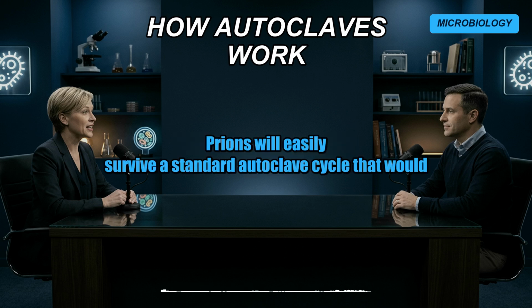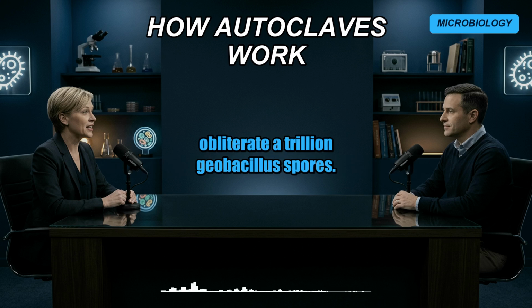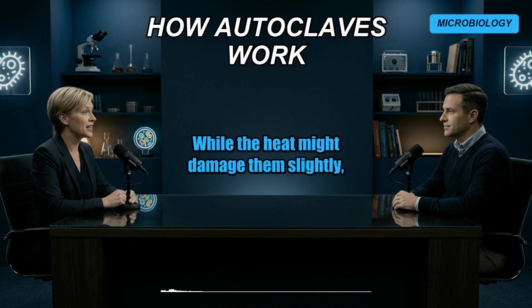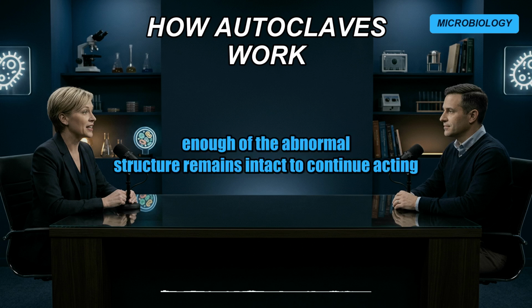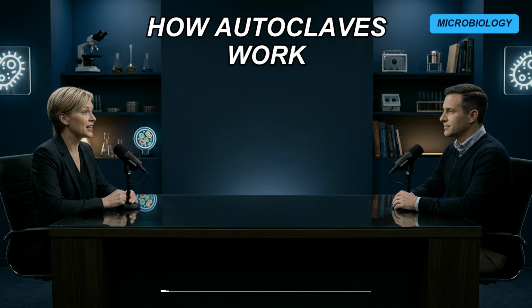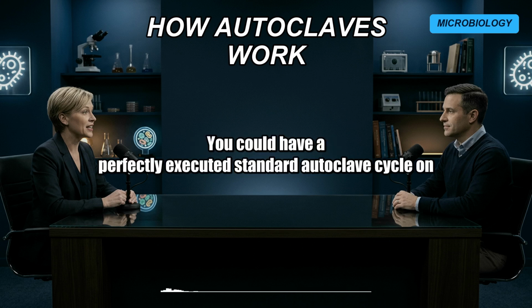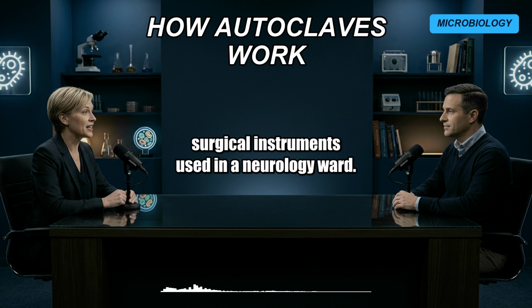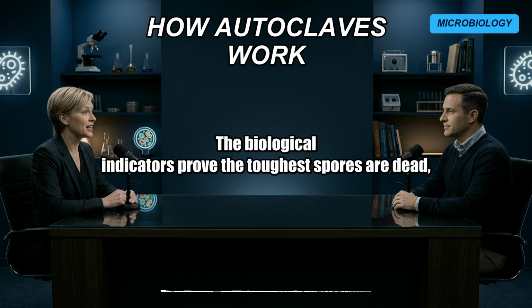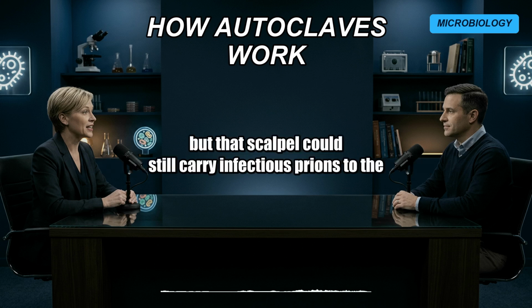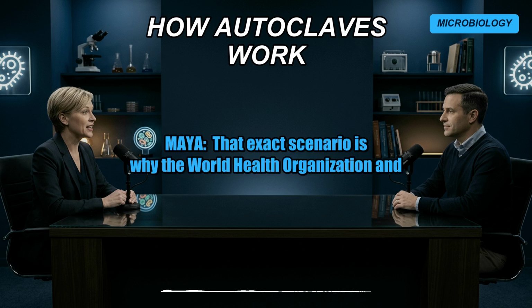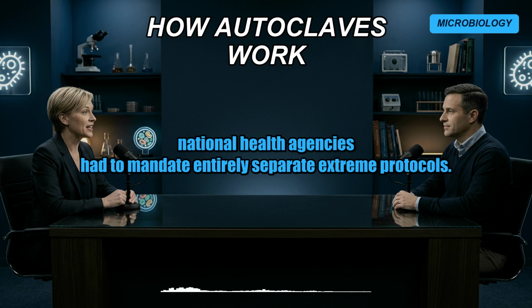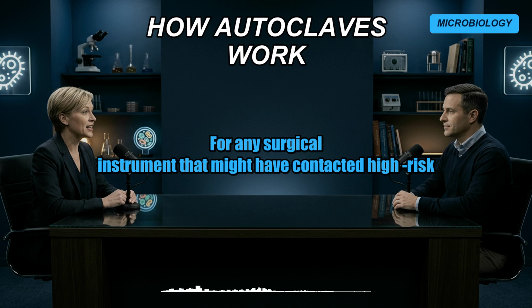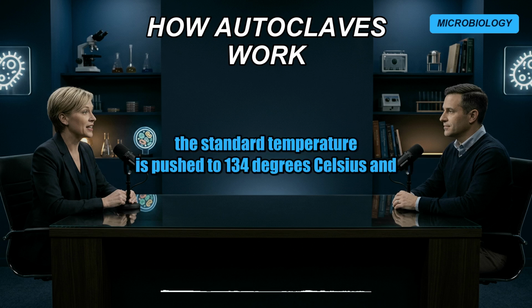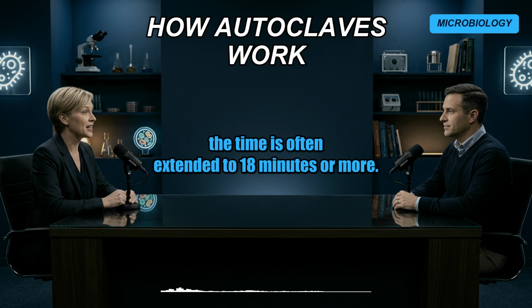Prions will easily survive a standard autoclave cycle that would obliterate 1 trillion Geobacillus spores. While the heat might damage them slightly, enough of the abnormal structure remains intact to continue acting as a corrupt template. That is deeply unsettling. You could have a perfectly executed standard autoclave cycle on surgical instruments used in a neurology ward. The biological indicators prove the toughest spores are dead, but that scalpel could still carry infectious prions to the next patient. That exact scenario is why the World Health Organization and national health agencies had to mandate entirely separate extreme protocols. For any surgical instrument that might have contacted high-risk tissues like the brain or spinal cord, the standard temperature is pushed to 134 degrees Celsius, and the time is often extended to 18 minutes or more.